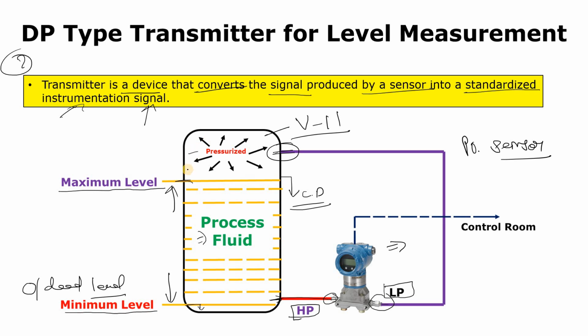At this portion you can see the tank is pressurized due to gas and air. Now, this transmitter has the ability to subtract your LP side pressure from the total pressure shown by the HP tapping. The total pressure is applied at the HP tapping, and this is my LP tapping. So when you subtract the LP tapping pressure from the HP tapping, you get the DP, that is the differential pressure. We will discuss that later.